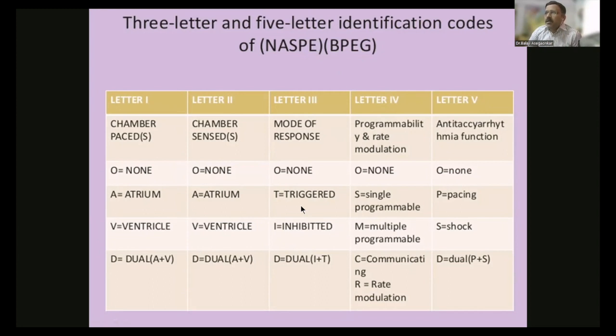In the fifth letter, antiarrhythmic function has been added. We can now put an artificial implantable cardiac defibrillator, with electrodes built into the pacemaker leads, which can give a shock, or cardiac resynchronization therapy can be given with a pacemaker. So this fifth letter represents antiarrhythmic function and resynchronization therapy.